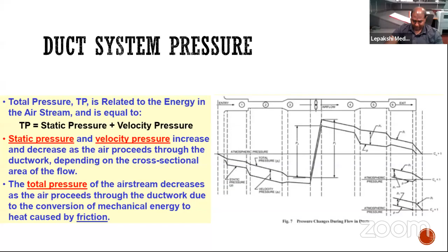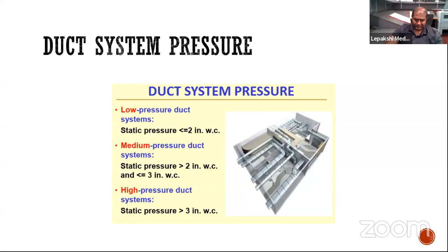You have different types of duct systems based upon the pressures being handled in the duct. If it is less than 2 inches of water column, they're considered low pressure ducts. Between 2 and 3, they're medium pressure, and anything more than 3 inches of water column of static pressure is considered a high pressure duct. You'll have friction losses and dynamic losses. Again, the ductworks are used to supply air. Air is a fluid and has viscosity, turbulence, and so on. You'll have friction losses, and the dynamic losses are from the fittings.